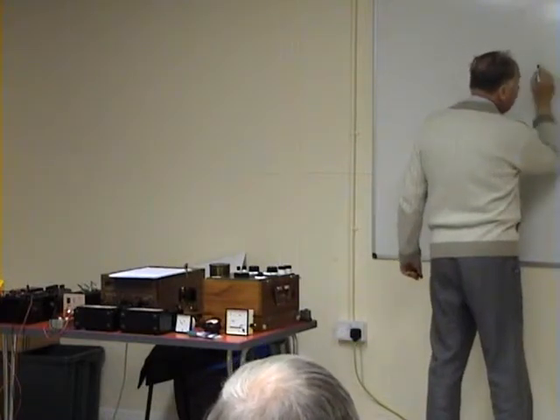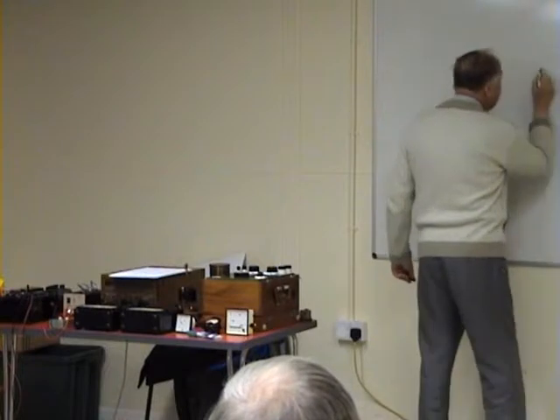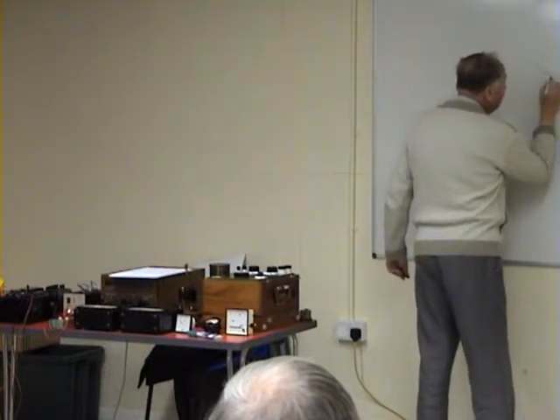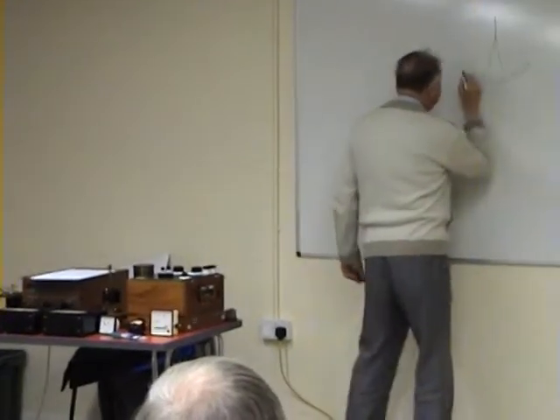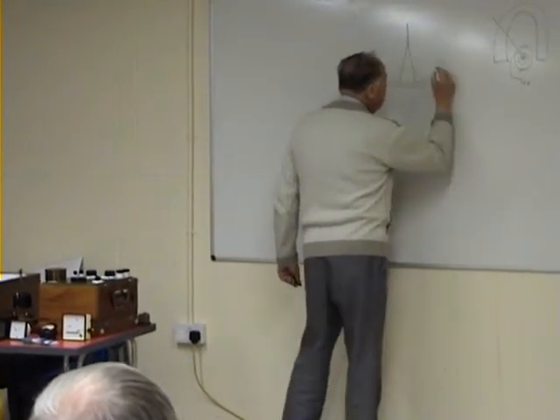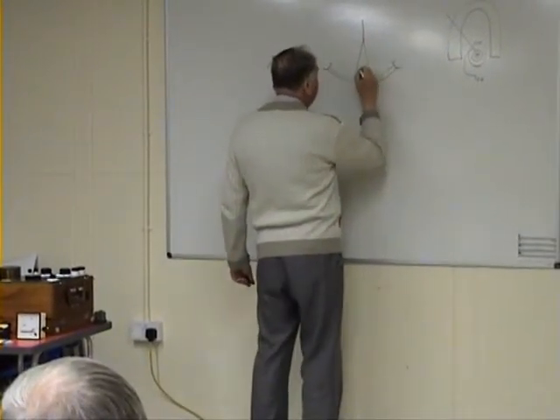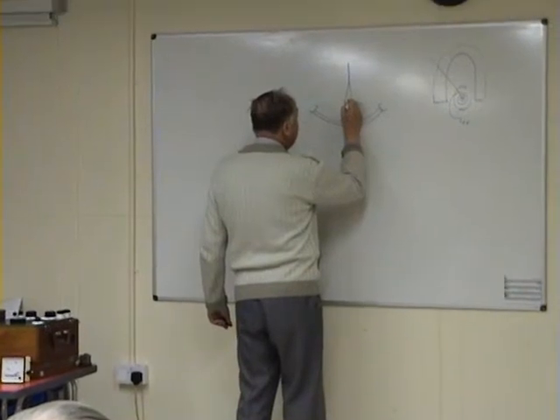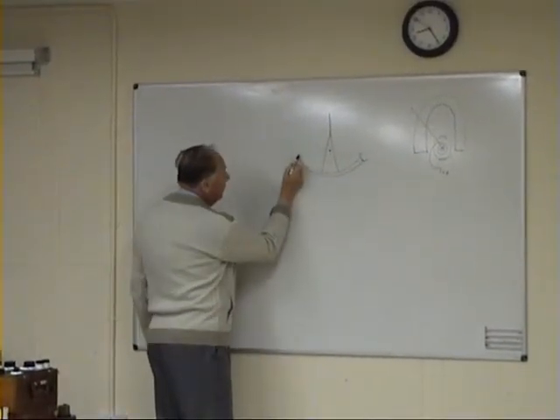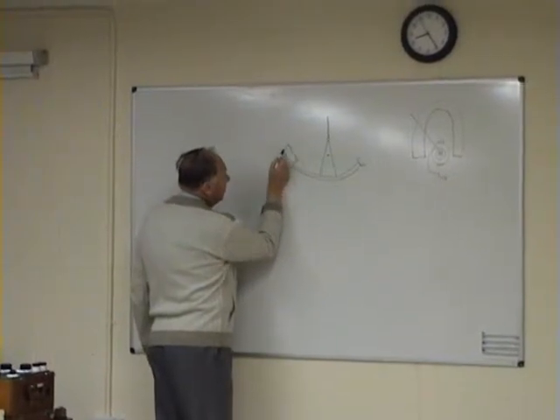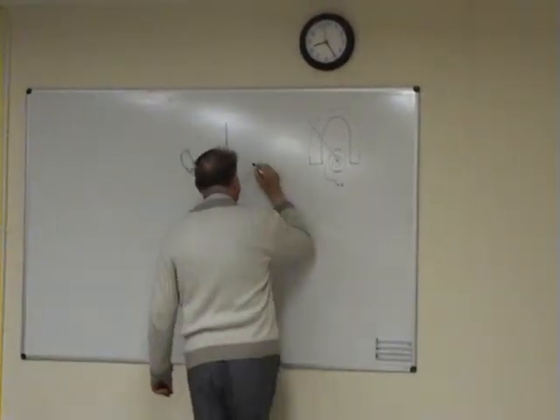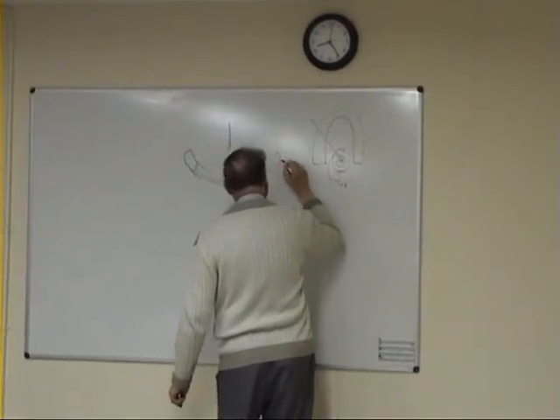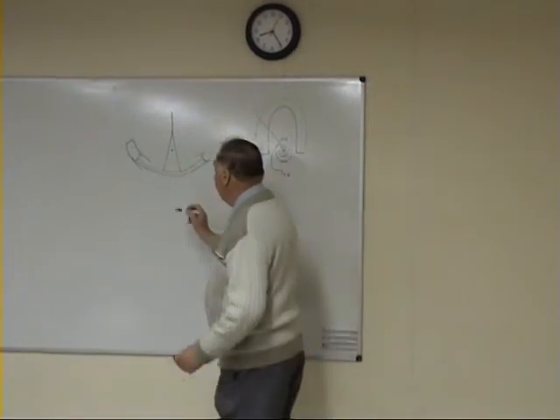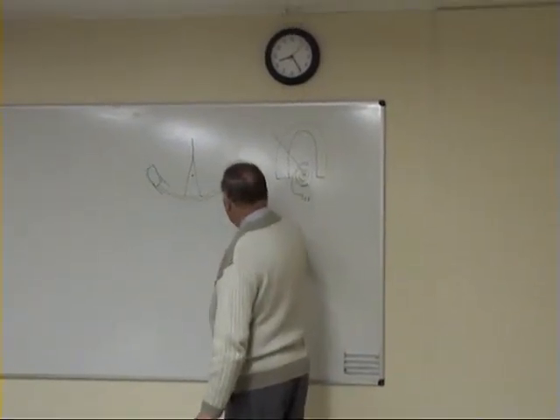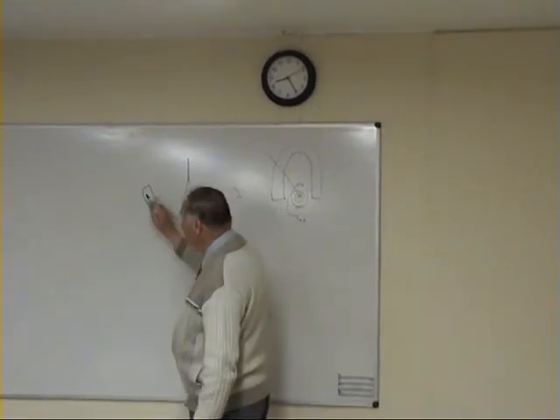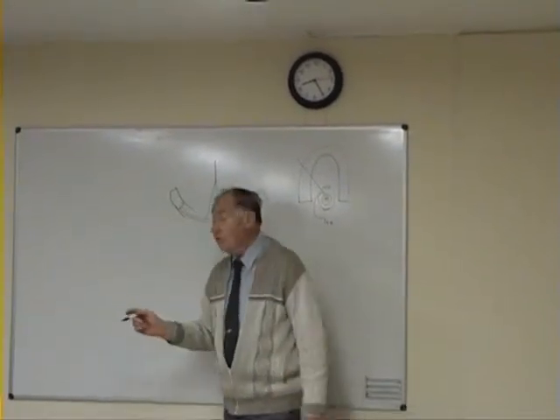An A-frame was welded to this anchor portion. On the end of the anchor portion were two aluminium cups. The pivot is somewhere about there. These then ran inside a moulded bakelite tube, which was the air damper. So this thing moved, and it controlled the movement that way, or when it swung back, so there were no violent excursions.